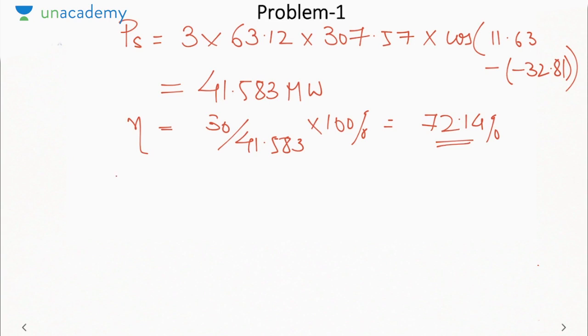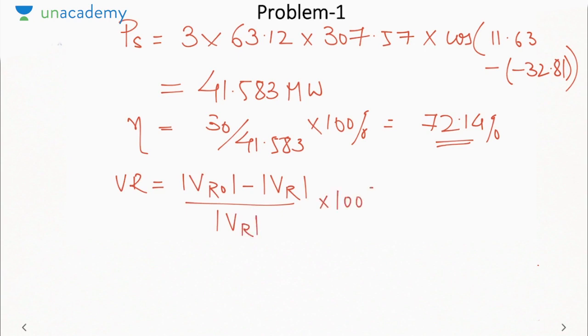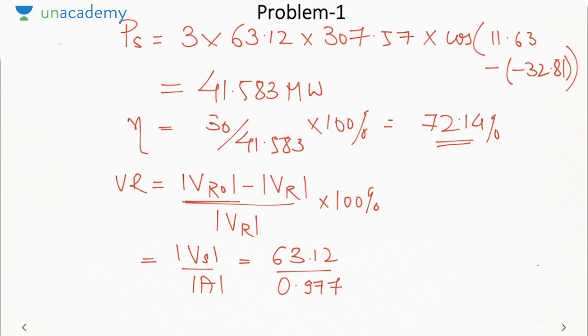Next, to calculate voltage regulation, we calculate like this: VR0 minus VR by VR into 100%. So we need VR0, which is mod Vs by mod A, 63.12 divided by 0.977. So this is 64.6 kV.